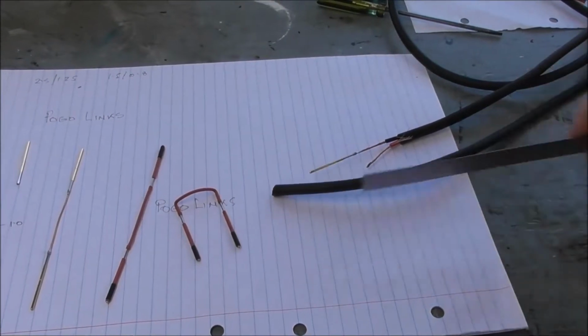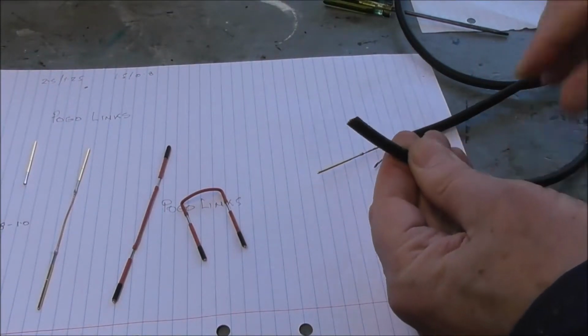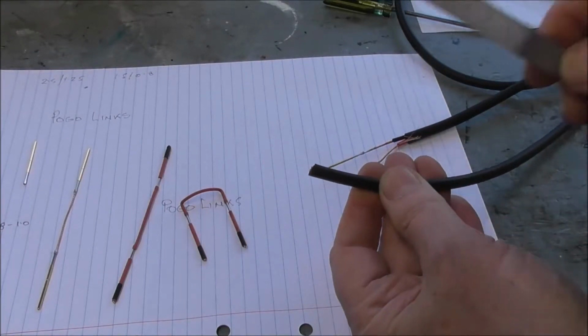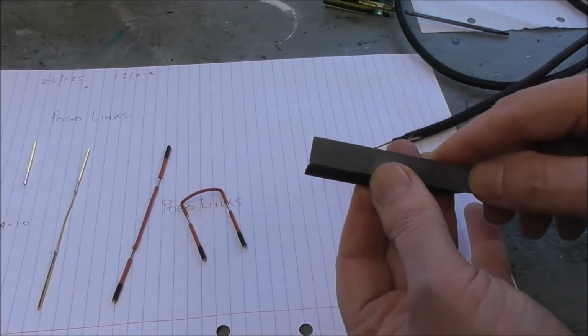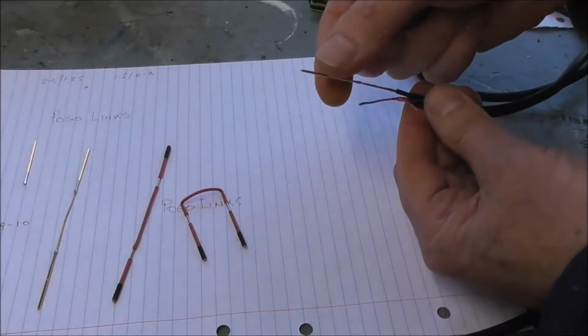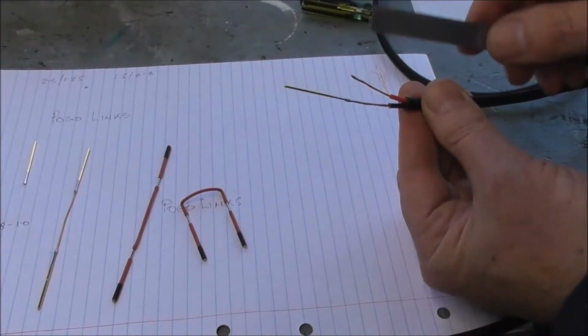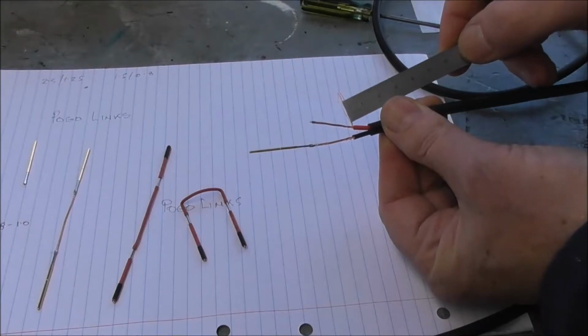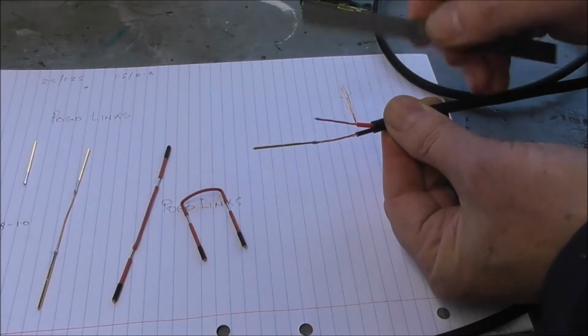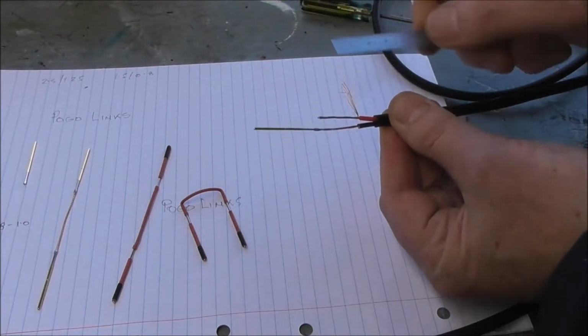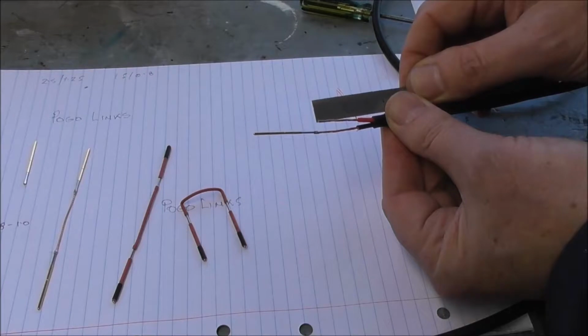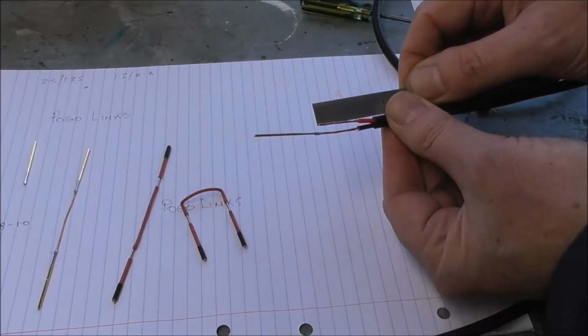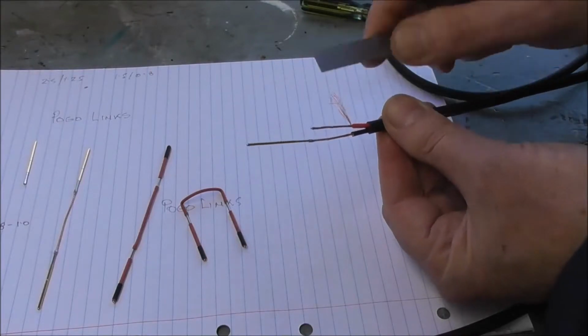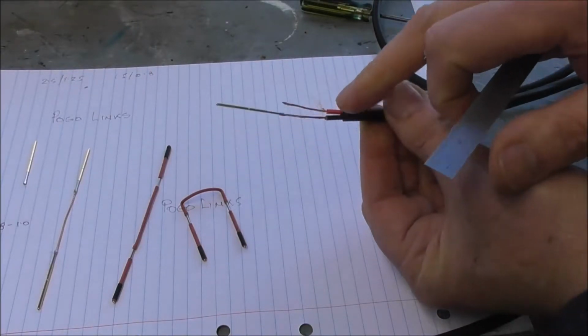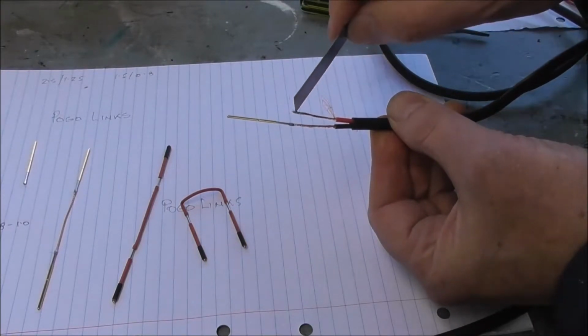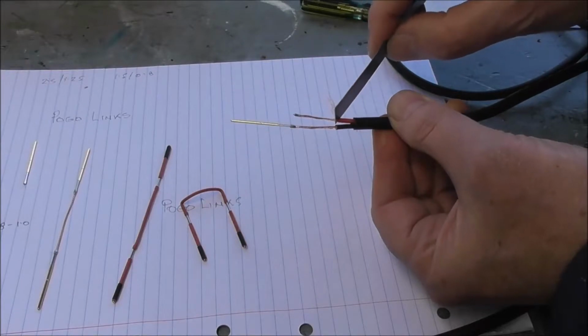Okay, so on the other end of the main cable, this is just cut off to start with there. Take the main outer insulation back a distance of 30 millimeters. So you end up with this situation, and then take the small diameter insulation back a distance of about 30 millimeters there, and about 22 millimeters off the end, so you've got about 8 millimeters here. Just checking you can see this okay. Alright, you've reduced it down from 30 to 22 with 8 millimeters of insulation.